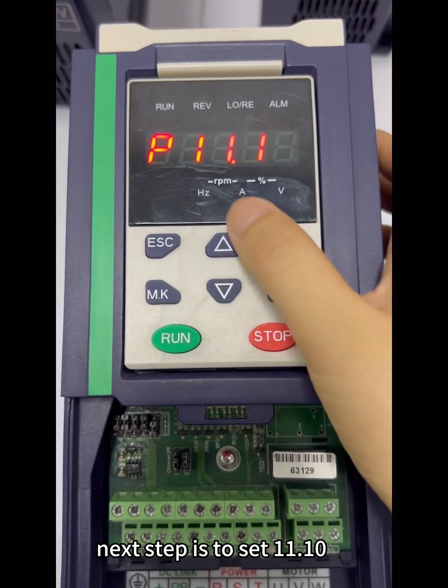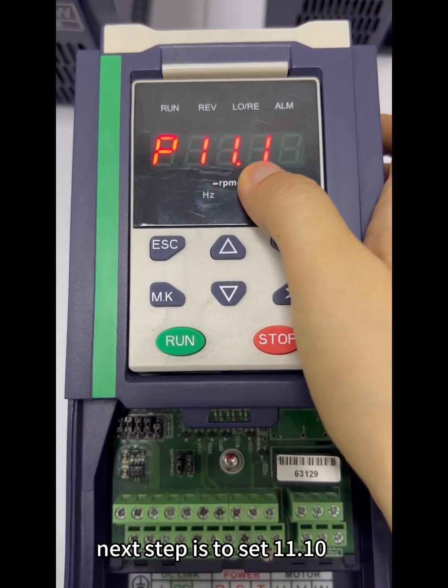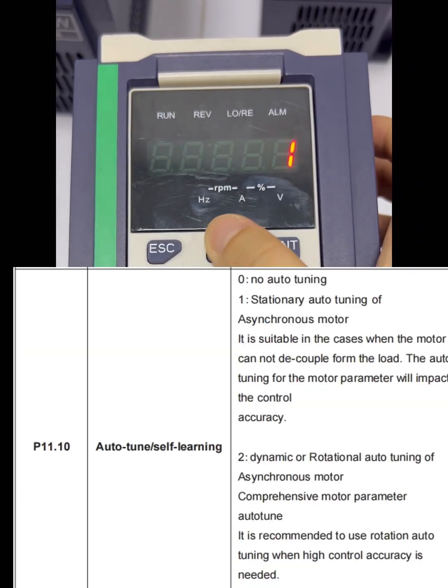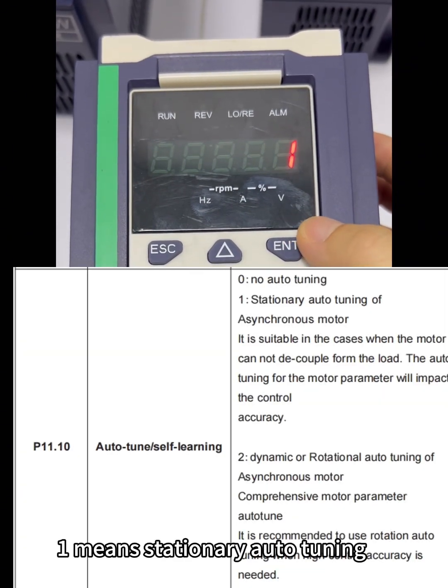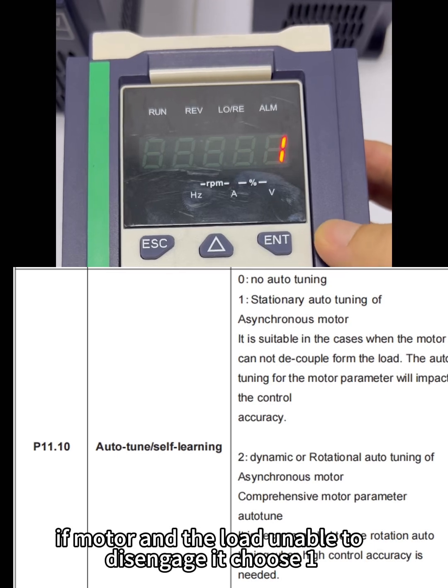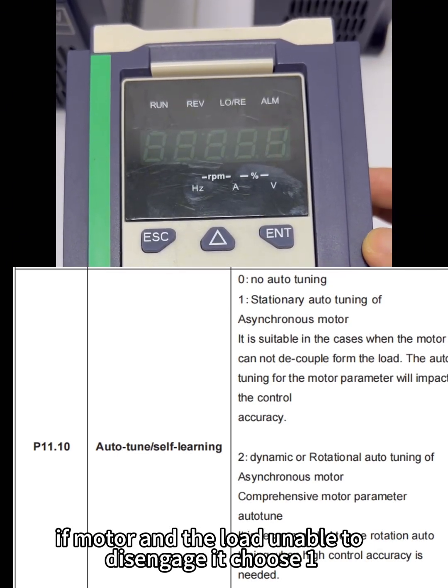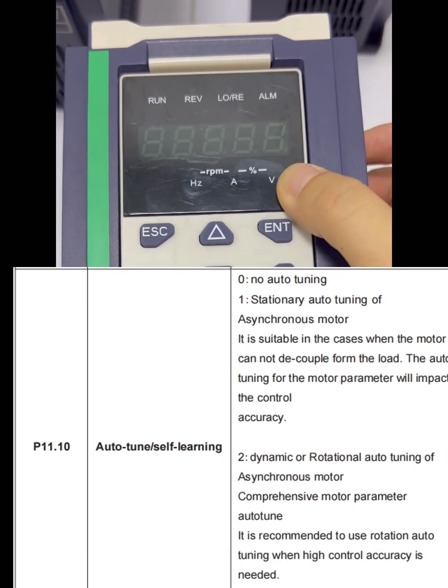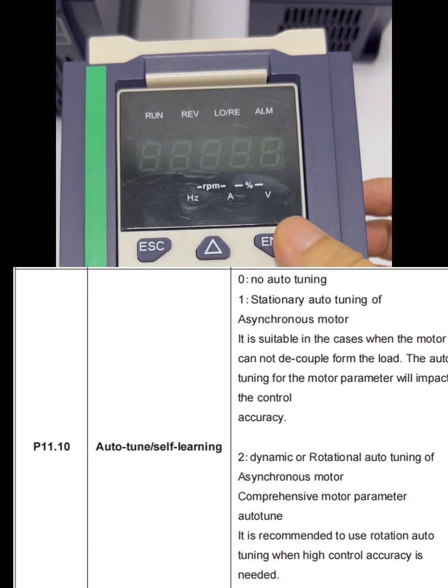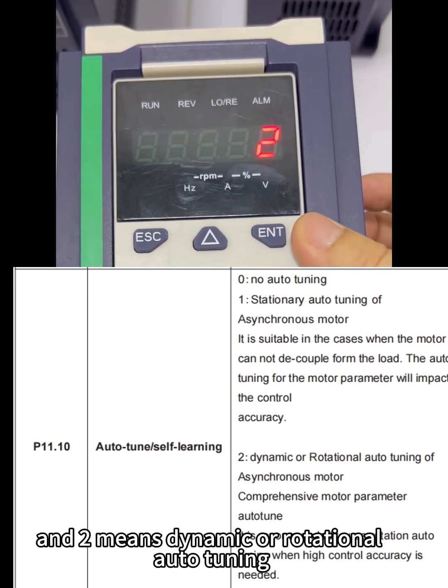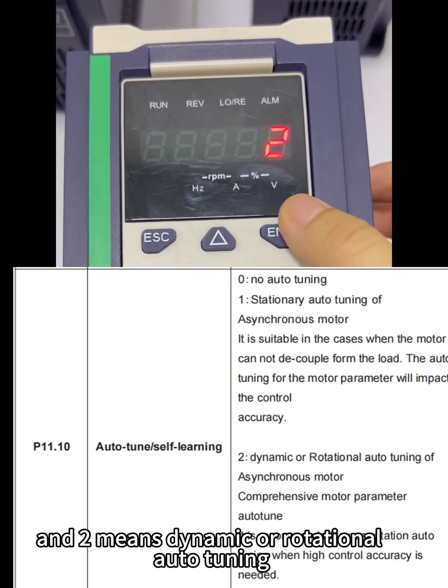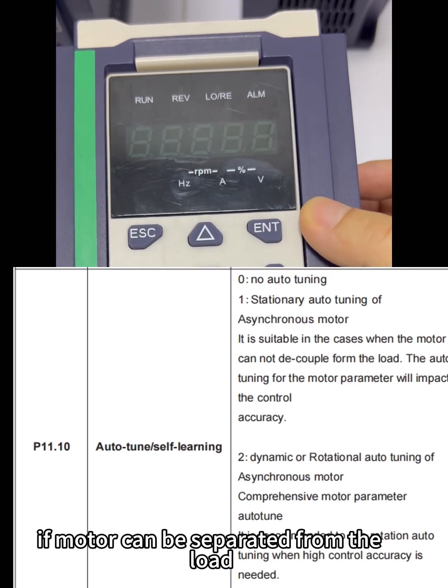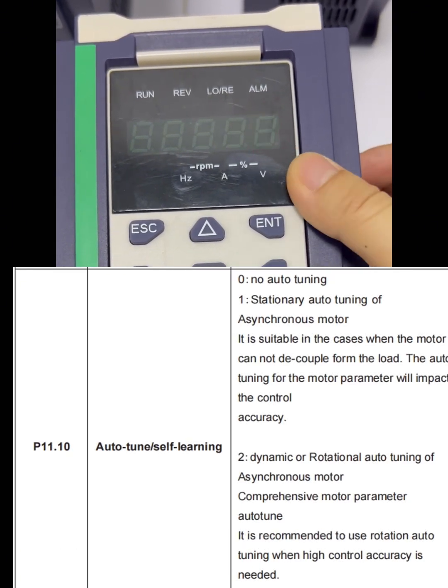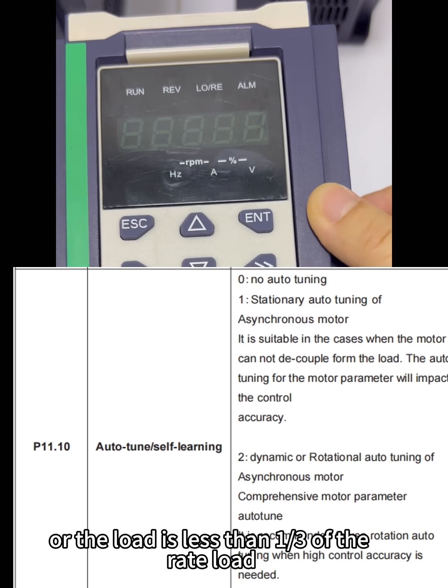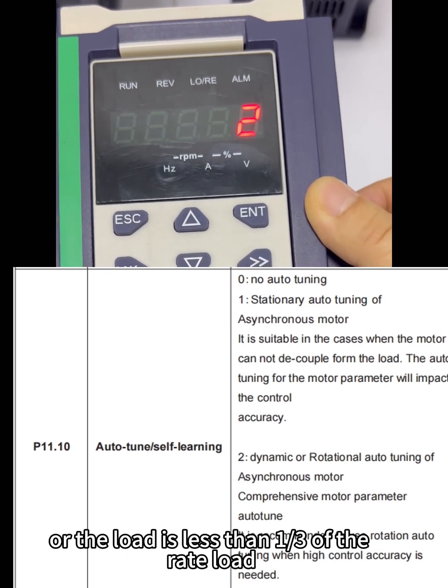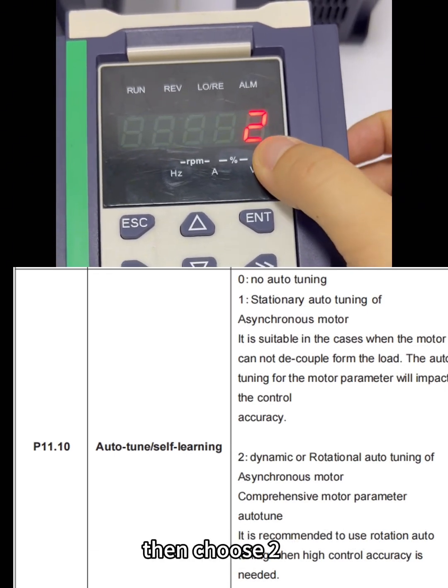Next step is to set 11.10. 1 means stationary auto-tuning. If motor and load are unable to disengage, it chooses 1. And 2 means dynamic or rotational auto-tuning. If motor can be separated from the load, or the load is less than 1/3 of the rate load, then choose 2.